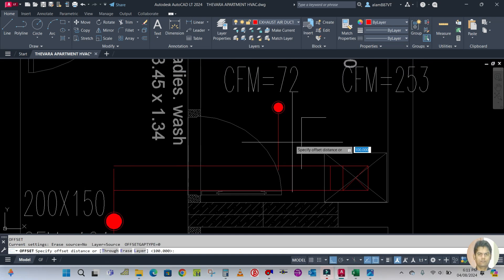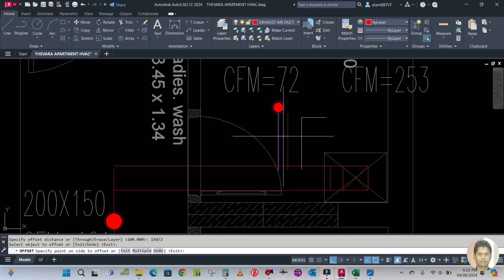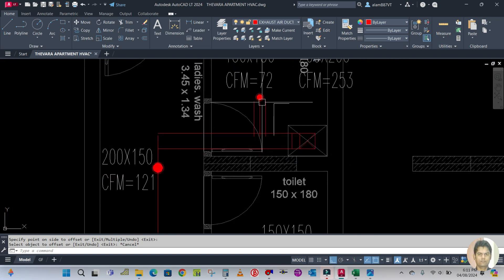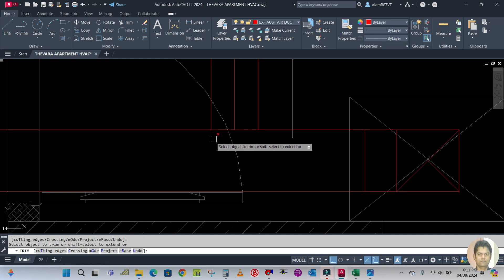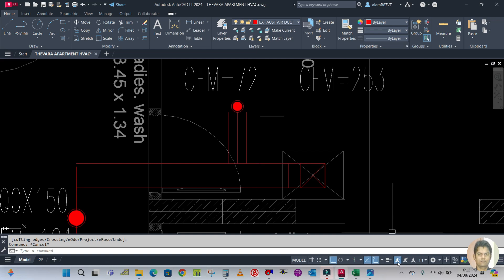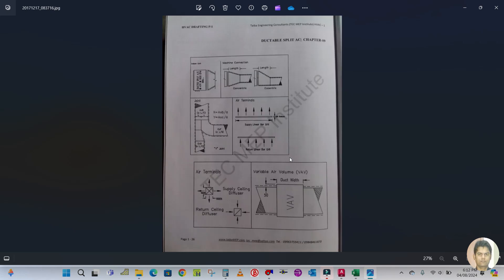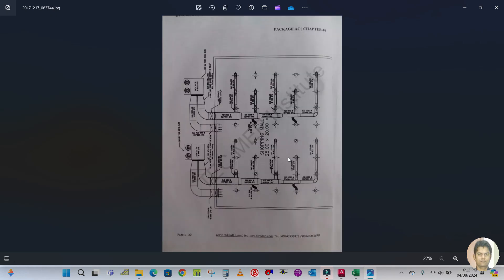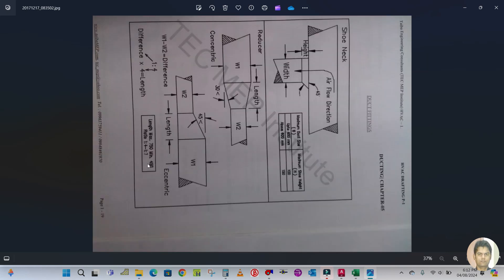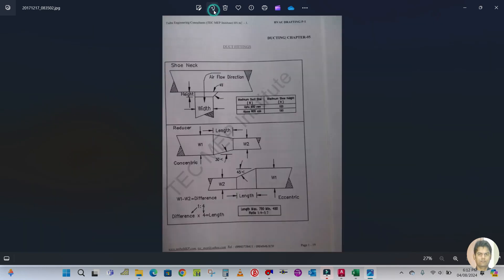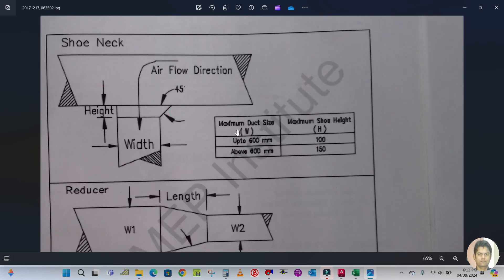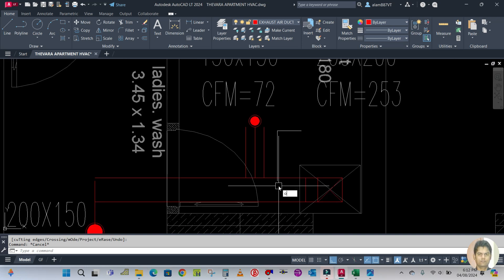Next is this branch, which is 6 inch — 150 divided by 2. I'll show you how to create the shoe neck. Trim this first using T, A, double Enter. The shoe neck: the maximum duct size up to 600 mm has a maximum shoe neck height of 100 mm, and above 600 mm it is 150 mm. Here our duct size is less than 600, so we make it 4 inch — 100 mm. Offset 100 mm.